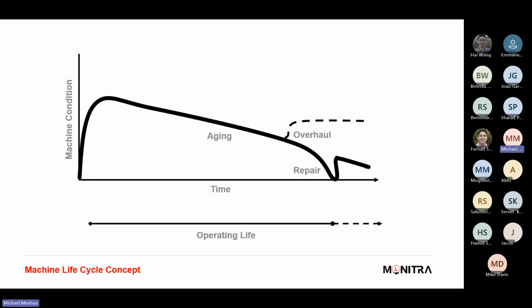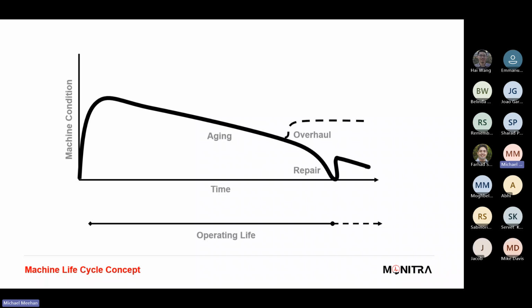through its operating life. Typical causes of that deterioration could be overloading, exceeding the machine's rated capacity can lead to overheating and therefore insulation breakdowns. Voltage imbalances, unequal voltage distribution can cause increased current in certain phases, leading to overheating and component failure. Harmonics, distorted current waveforms can generate additional heating and stress on the machine. Starting and stop cycles, probably one of the most arduous. Frequent starts and stops can accelerate wear and tear on the components. Environmental conditions, exposure to extreme temperatures, humidity, contamination, or vibrations can also degrade the machine components.